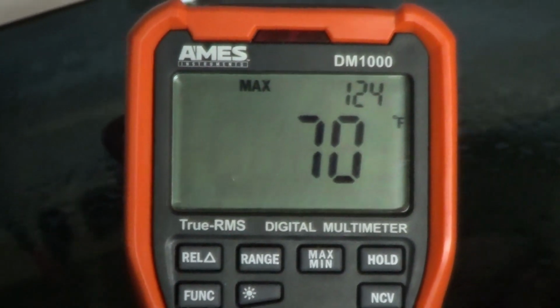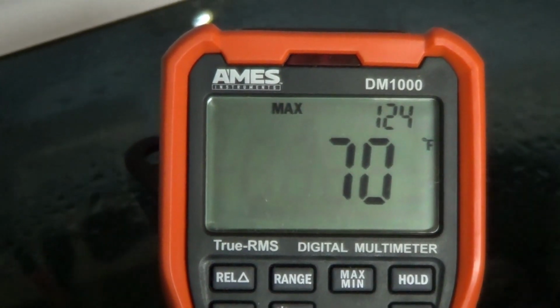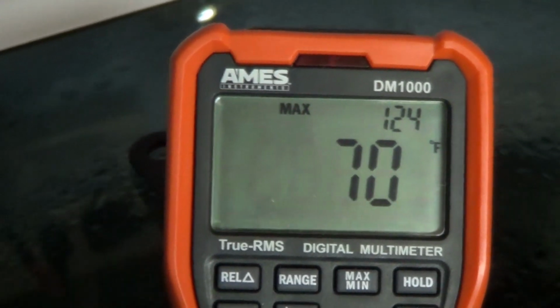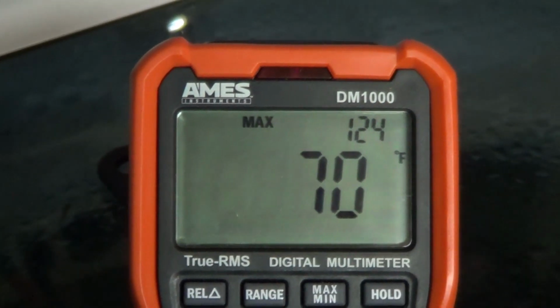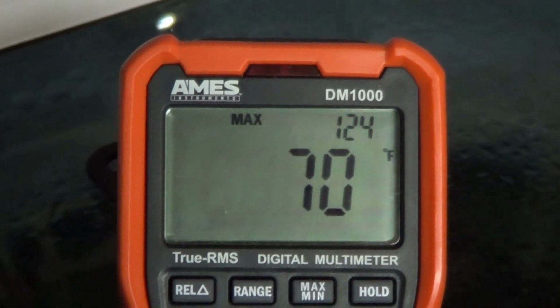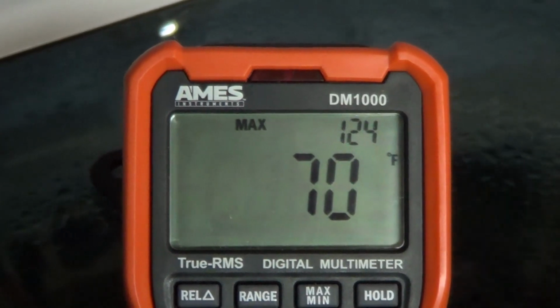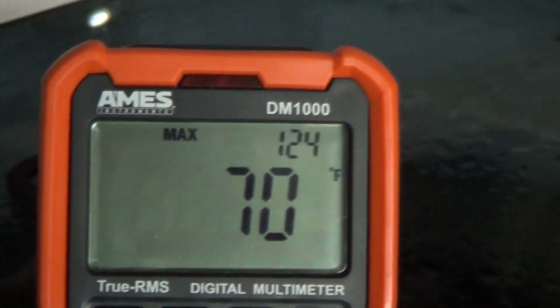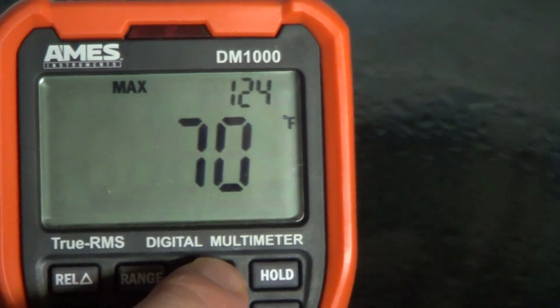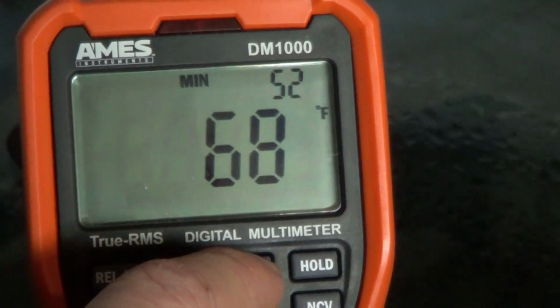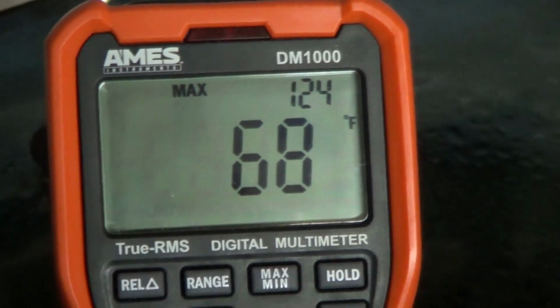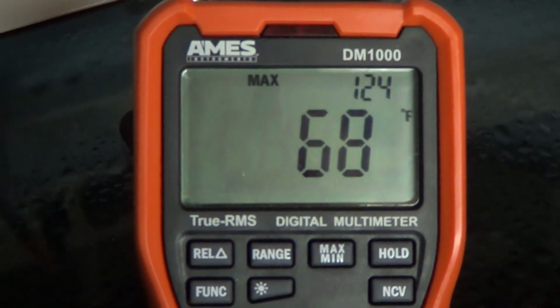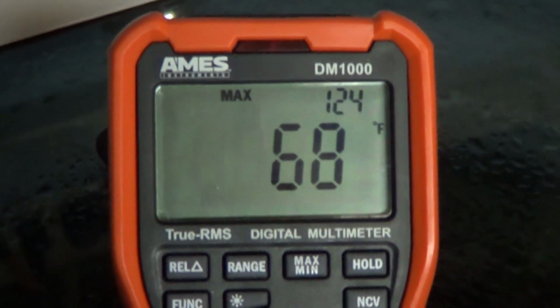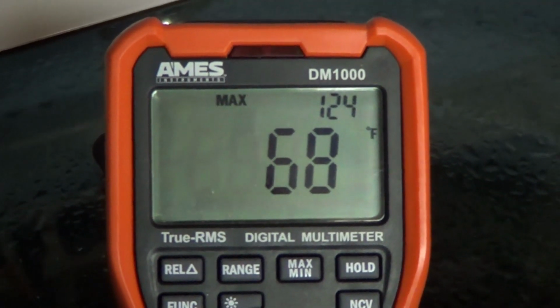It turns out that the secondary display on the Ames Instruments DM1000 multimeter does actually have a few more uses than simply displaying frequency and duty cycle readings when you're measuring alternating current. It's also used when you're operating the meter in its minimum and maximum mode to indicate the minimum and maximum readings that it has seen over a period of time. This is actually pretty convenient because it leaves the primary display active and able to display the currently indicated reading.